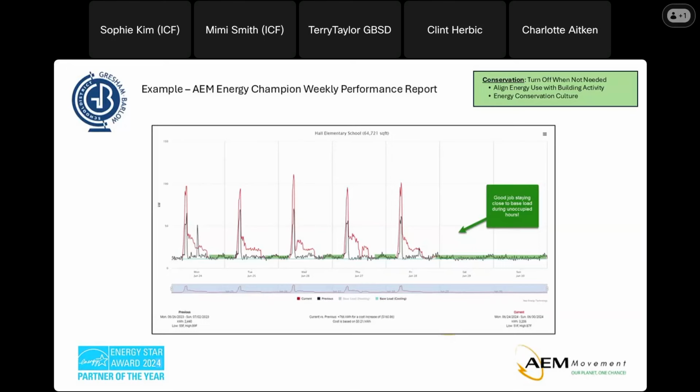It's an electrically heated, electrically air conditioned school. The high spike you see for us is, to Clint's point earlier, our systems are set to run every day. We don't do a lot of shutdowns across the summer. We run 1 hour in the morning to flush the building out, in case it was hot or cold, to keep the air circulation. It also keeps the HVAC running. Our mechanical folks do not want us to shut it down wholeheartedly, in the fears that Clint talked about earlier. We want to make sure that it starts. So this really shows that this building's performing. Next slide.